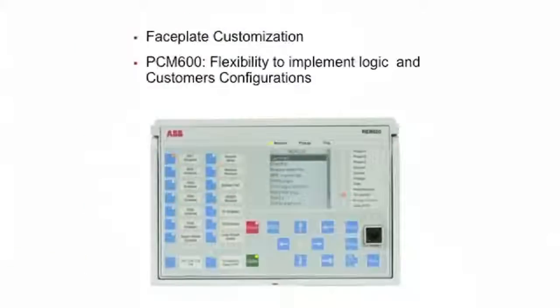In their system, the operators are used to, when they push the button, they actually disable the ground block. So these small differences, when talking about having an issue on the field, the operator is already used to something. So the benefit of having the flexibility to program the push button is that we could take all these push buttons and LEDs and program it in a way that is easier for your operators to use. So we could sit down with you and say, okay, what are your operators used to now? We could change the LEDs allocation, how they're configured, the push buttons. Obviously the labels are configurable, but we can actually program a lot of the logic on the faceplate to make it easier for your operators to use.